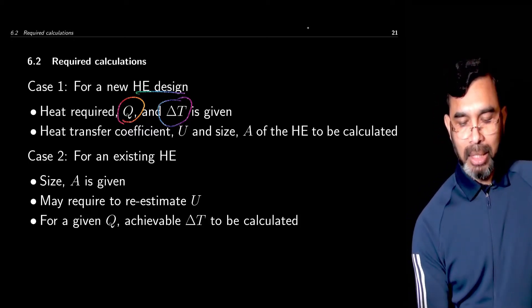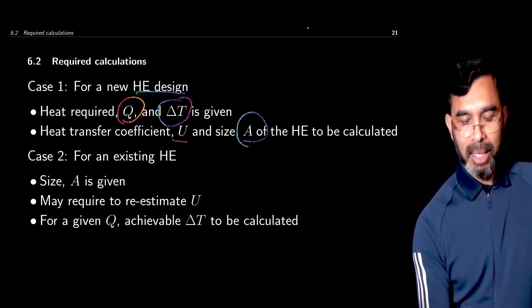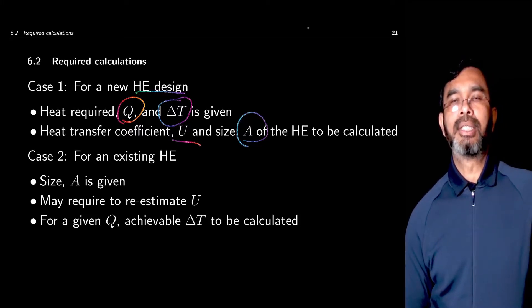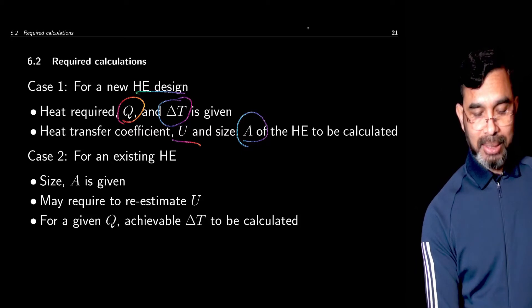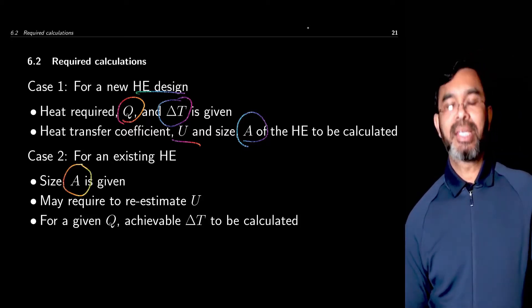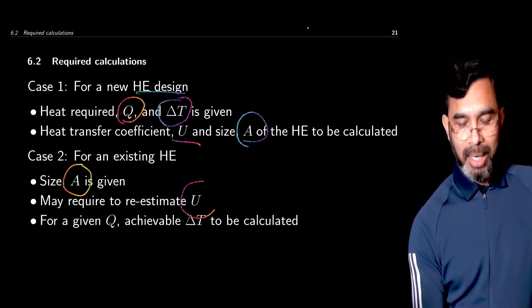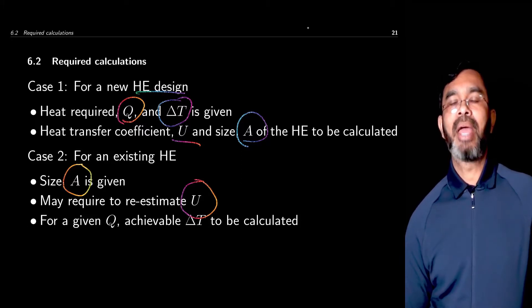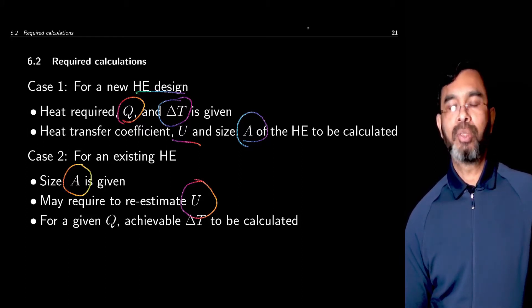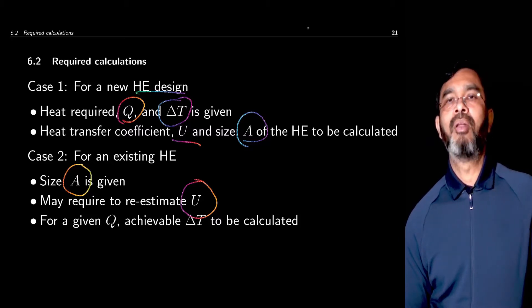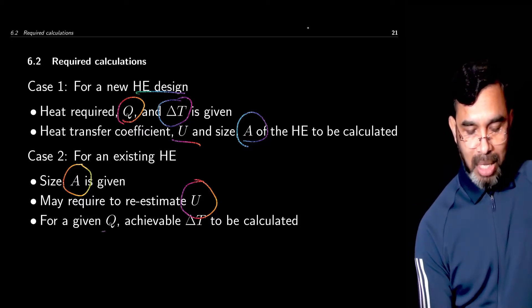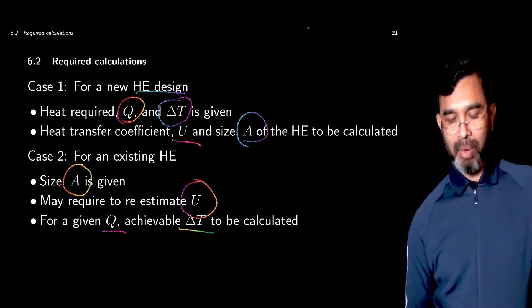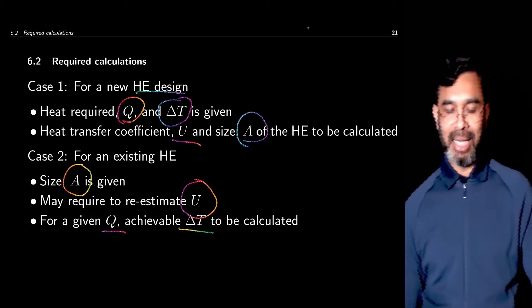For a new design, we need to determine the size of the heat exchanger and the resulting overall heat transfer coefficient. For an existing heat exchanger, the size is given, so we may need to re-estimate the overall heat transfer coefficient. This may happen because there may be significant fouling, and we need to determine whether the extent of fouling is acceptable or whether we need to clean the heat exchanger. So for a given Q, we may need to calculate the achievable delta T.